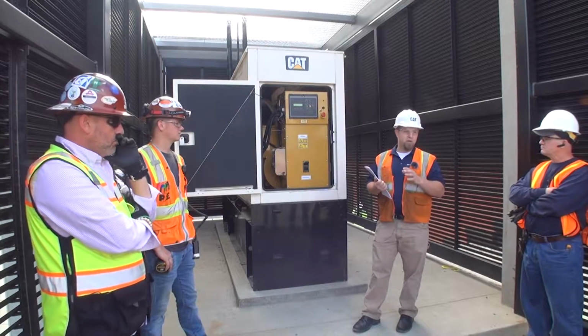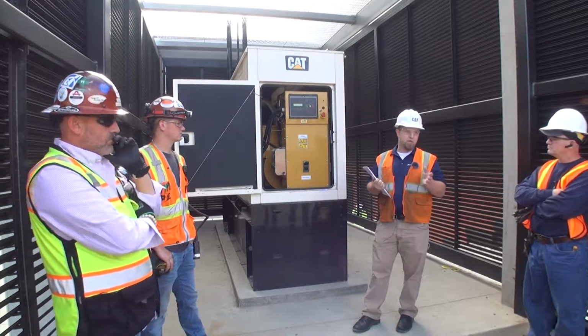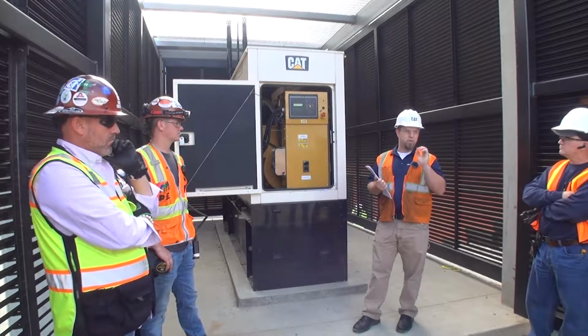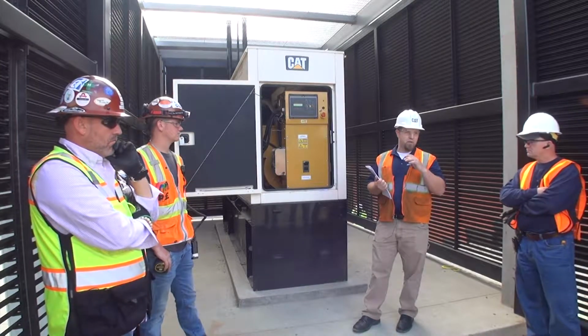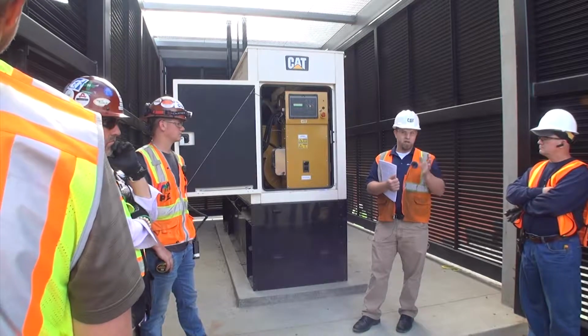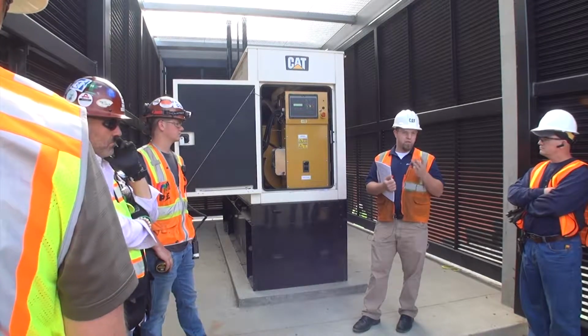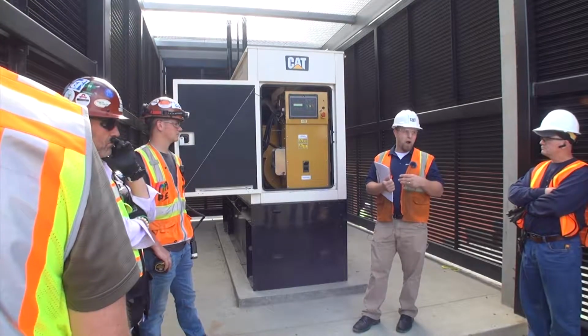Now, if you were doing your building transfers every month religiously like you're supposed to, and you could show it was above 30% every month, you can get away from doing the yearly load bank and move to a 3rd year load bank, which is a 4-hour load bank.